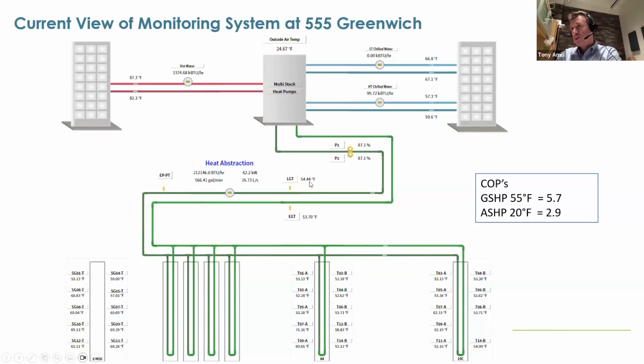Leaving, going into the heat pumps was about 54.44. So when you do a coefficient of performance, what you see here is if the air source heat pumps were delivering all the heating today, on this particular day, we would only get an efficiency of 2.9. So for every 1 unit of electricity produced, we're going to deliver 2.9 units of heat. Whereas with the ground source heat pump, we were going to get 5.7 units of heat from that 1 kilowatt, that 1 unit of electrical energy.